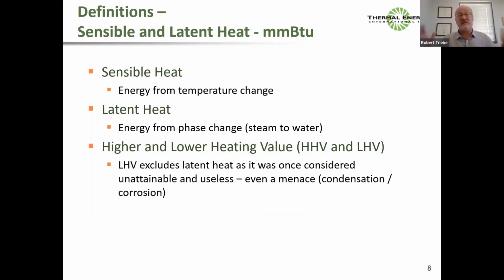So sensible heat is energy from a temperature change. Latent heat is energy from a phase change. Interestingly, these also define the difference between higher and lower heating value. Lower heating value is basically the heating value of the fuel excluding the latent heat. And the reason the concept of lower heating value was invented was because latent heat was considered unattainable and useless.